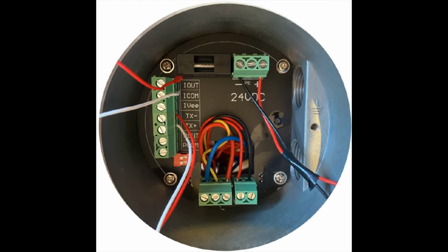This is the RS485 plus and minus. This is the 4 to 20 plus minus. And this 4 to 20 is self-powered, meaning do not put 24 volts into this device. This device takes more than 4 milliamps to run, therefore it's not a loop-powered device. So the 4 to 20 is you configure your PLC as though it were a Fluke meter. So that's a self-powered device, and that's it.